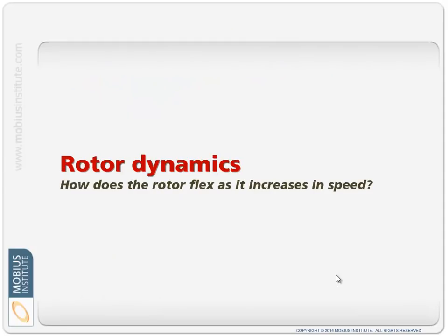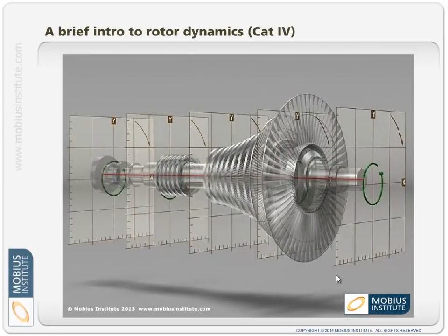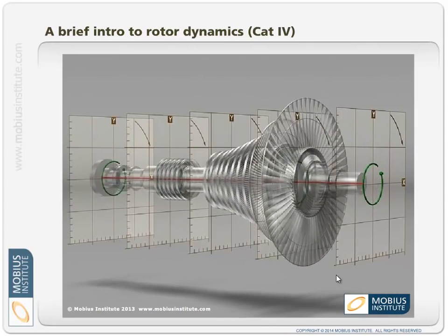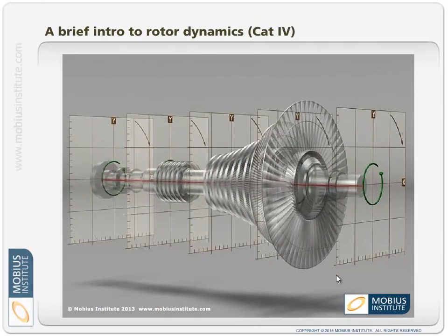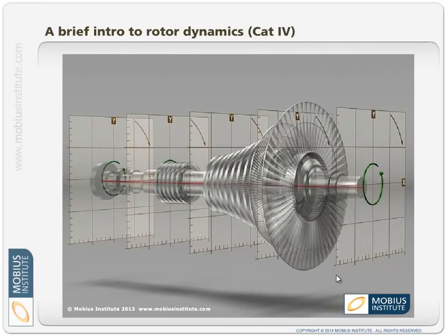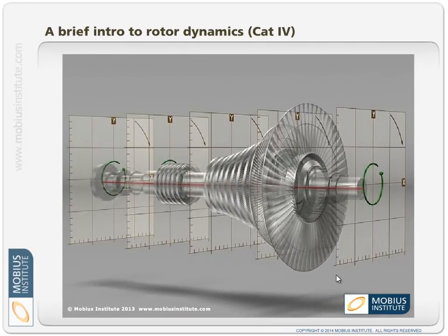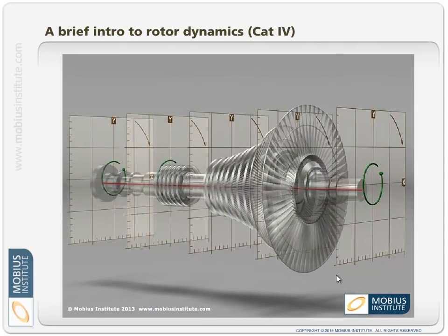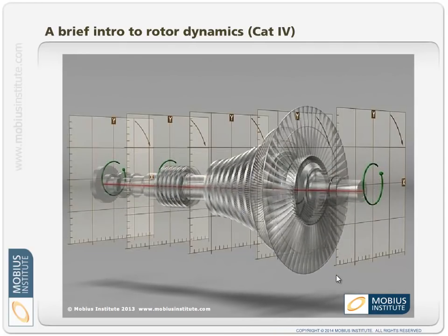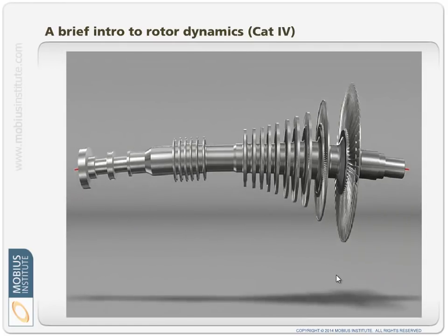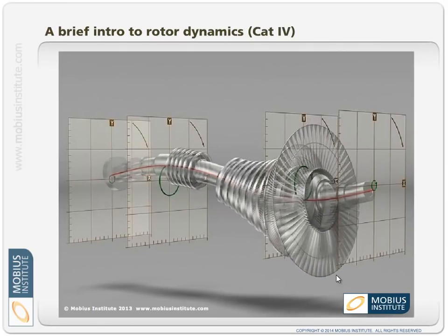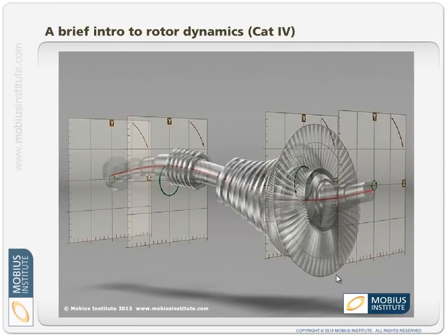Okay, so I'm just going to very briefly mention rotor dynamics. Now, we've mentioned it a little bit so far, because the fact is that while we are interested in what's happening at each of the bearings, that is of great interest to us, we're interested in rubs, we're interested in stability and these sorts of things, we're very, very interested in what the whole rotor is doing. And in this case, we've mimicked having five sets of prox probes just for the sake of mimicking it, and you can see that the motion is the same at each of them, so the orbit shape and size is the same. But depending on the motion, that can give us orbits that look quite different. And in this case, you can see that there's a phase relationship as well.